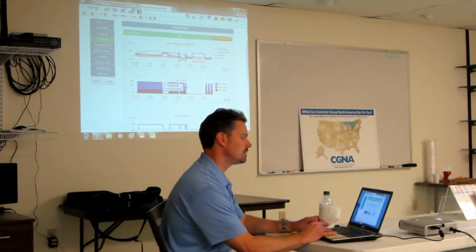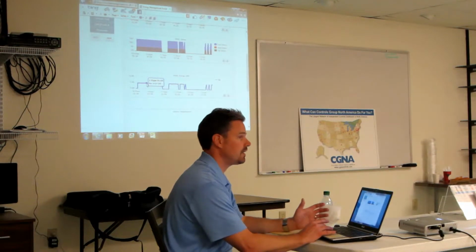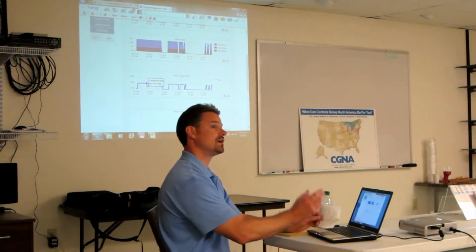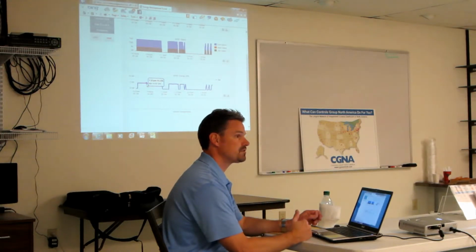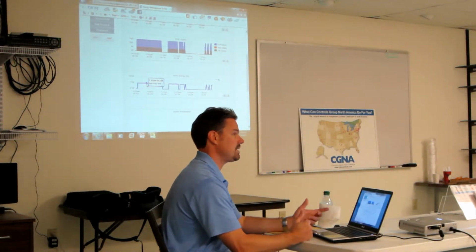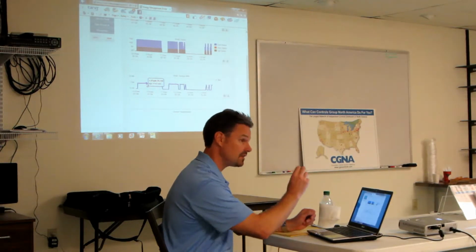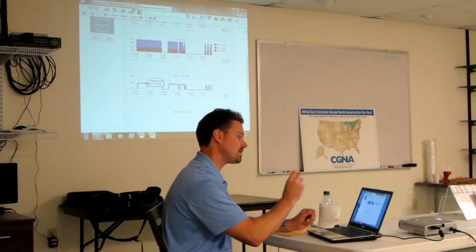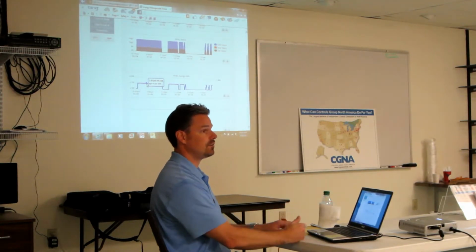Okay. Down here below, it's graphing for you your energy associated with those calls. So you can see how much kW it's drawing when it runs. Now, what's nice about this too is, you get a call from your customer that's on this system, and they say, hey, it's not cooling off in here. It's 80 degrees, feels like the system's not cooling. You can look at this. You can actually see what temperature it is in there right now. What are the set points? You can see if it's calling. And then down here, you can see if there's energy associated with that call.